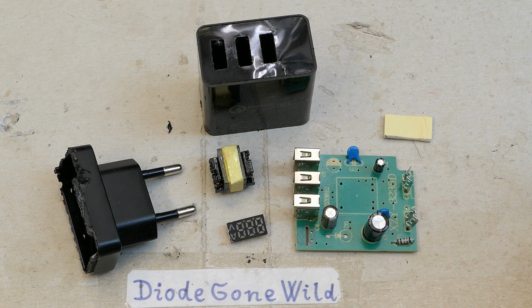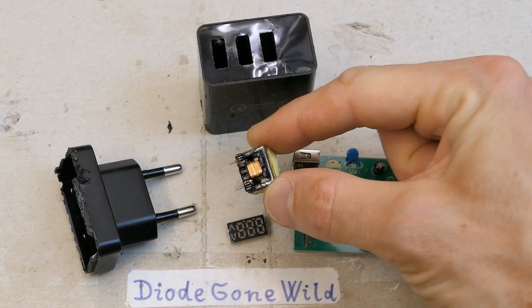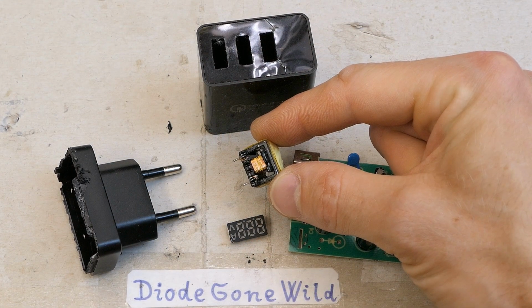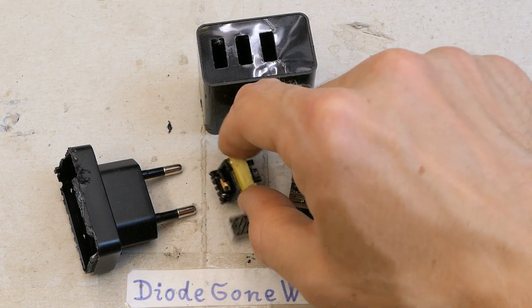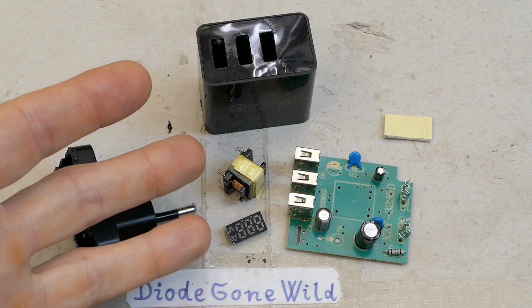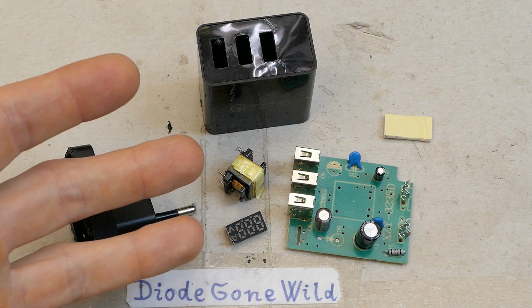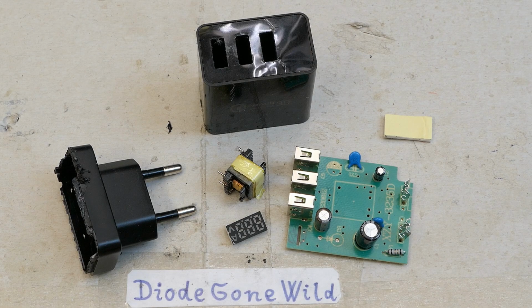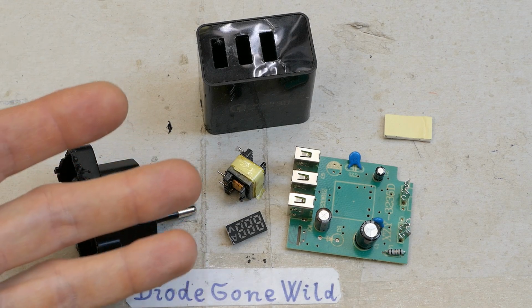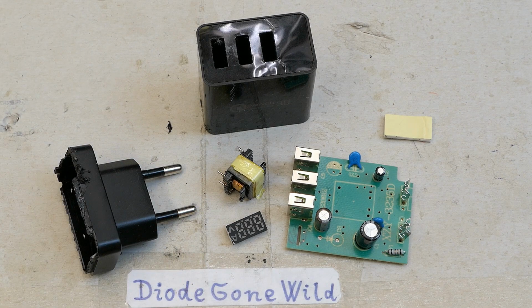But most importantly, there are several places in the transformer where the user is isolated from mains just by the lacquer on the wire — standard lacquer, not meant for applications where its failure could lead to an electric shock. There's no safety-insulated wire with thick double or triple insulation.